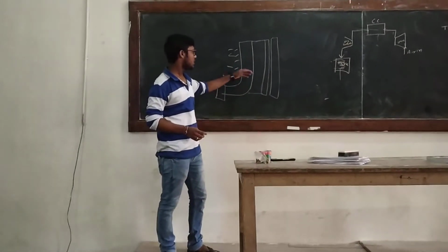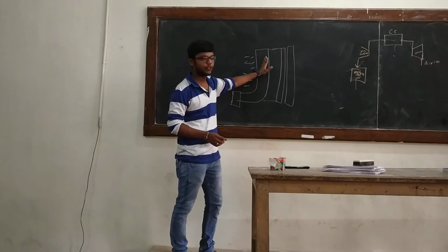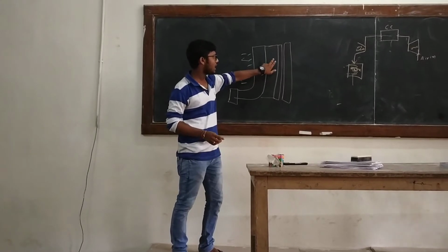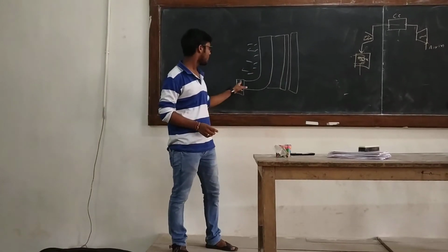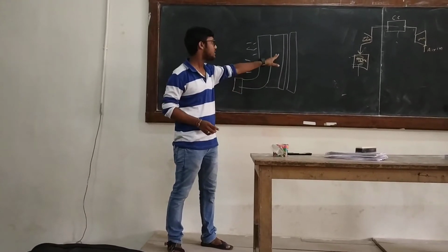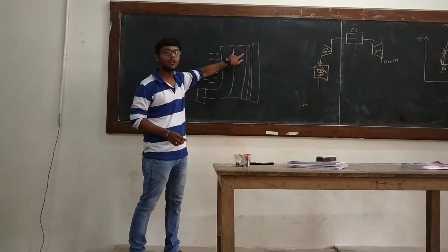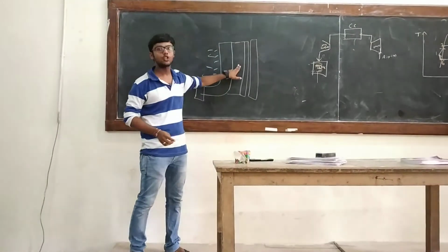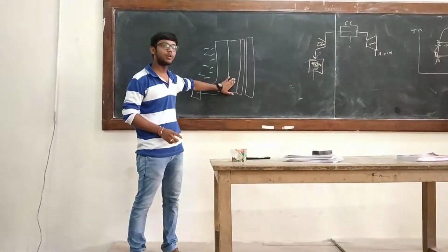material. As the furnace is used, the lining material goes on decreasing in thickness due to erosion of this refractory material. As the thickness decreases, its resistance to the current reduces, so by passing the current we can measure the resistance and hence see the thickness of the lining material. The furnace is designed for a particular lining thickness, and when the thickness is very low, the lining material should be changed. In the casting process, after almost 300 to 400 cycles, this lining material is changed.